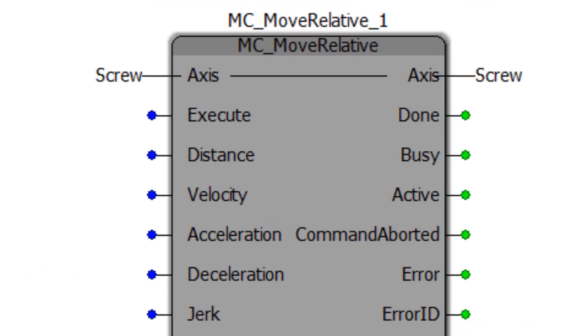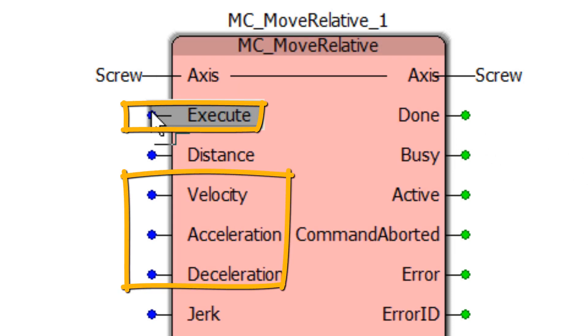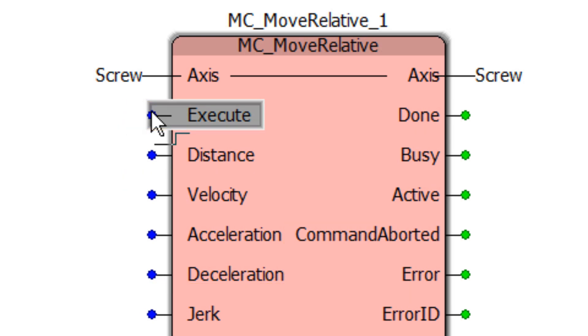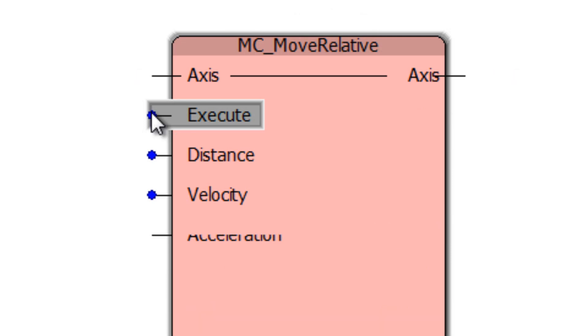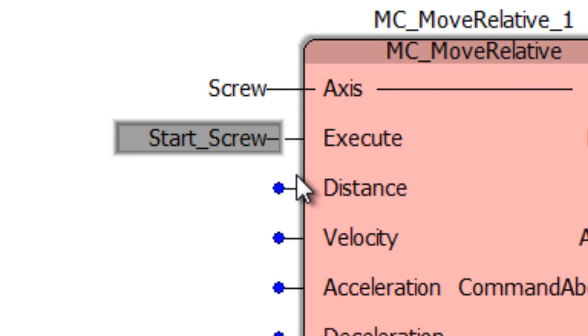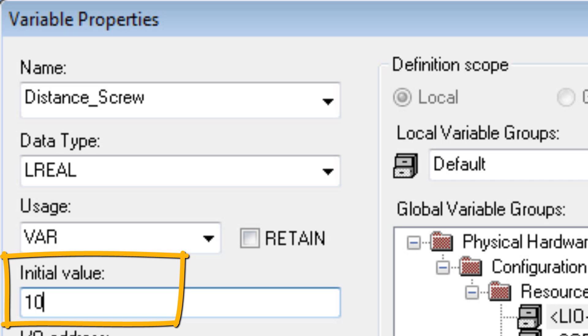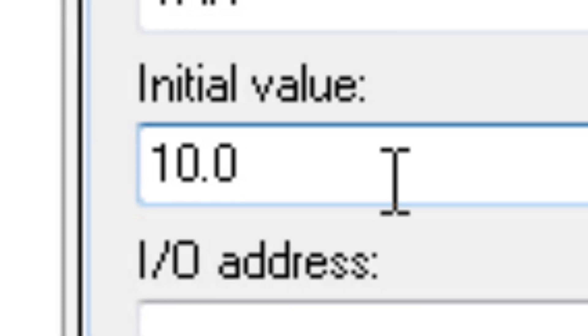For motion to occur there must be an execute input as well as non-zero values for velocity, acceleration, and deceleration. Double-click on the color dot to attach a variable. At execute, the variable name can be "start_screw", a local variable — the data type is chosen automatically. At distance, the variable name can be "distance_screw", with an initial value of 10 millimeters. It is important to use the IEC syntax 10.0 since the data type is LREAL.